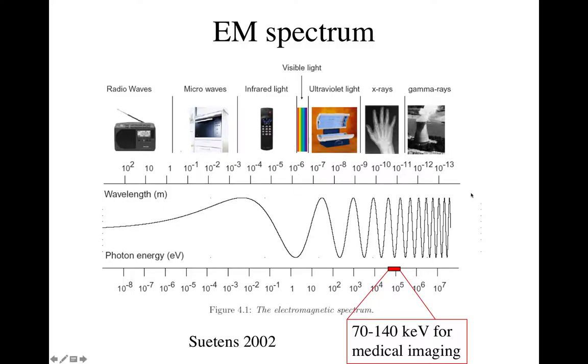X-rays are part of the electromagnetic spectrum, up here in terms of energy and wavelength. For diagnostic imaging, the X-rays we're interested in currently fall between 70 and 140 keV. There are X-rays of lower energy impinging on the patient, but they rarely get through — at lower energies, photoelectric absorption gets really high and most of those X-rays are absorbed; they just go to dose. You'd actually like to filter them away before shining them on the patient.